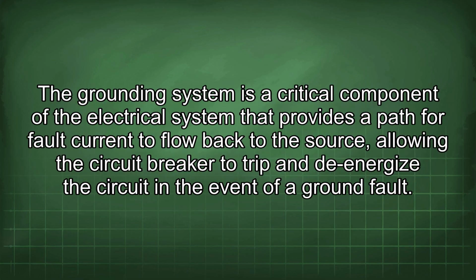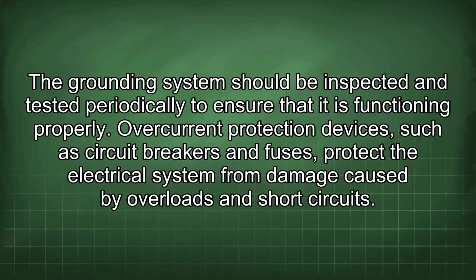The grounding system is a critical component of the electrical system that provides a path for fault current to flow back to the source, allowing the circuit breaker to trip and de-energize the circuit in the event of a ground fault. The grounding system should be inspected and tested periodically to ensure that it is functioning properly.